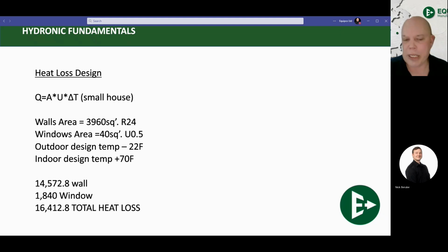Now, I didn't include the ceiling on this particular heat loss calculation, but that needs to be taken into consideration when you are doing one of these for real. Thing about it is, ceilings and attics usually get very, very thick insulation. I've seen R40, R70 in ceilings and attics, so it's usually a very small heat load through the ceilings. So it's usually not a huge factor here.